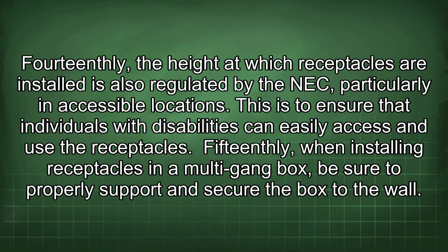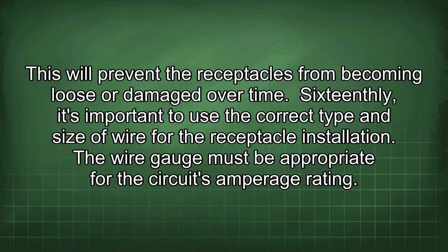15thly, when installing receptacles in a multi-gang box, be sure to properly support and secure the box to the wall. This will prevent the receptacles from becoming loose or damaged over time.